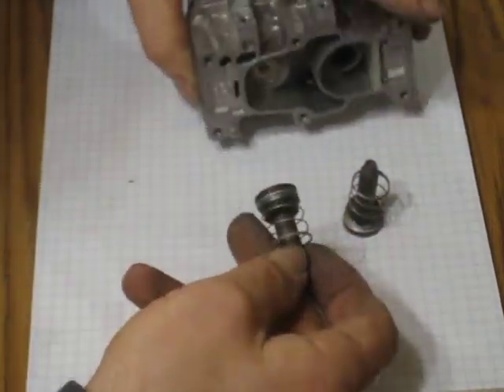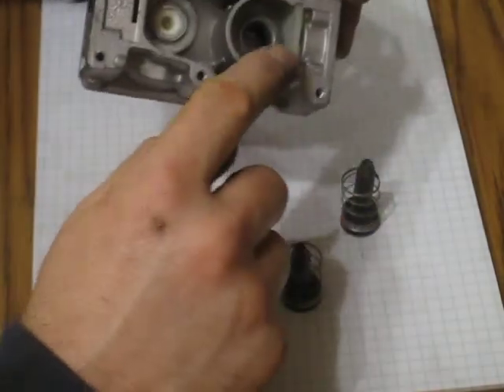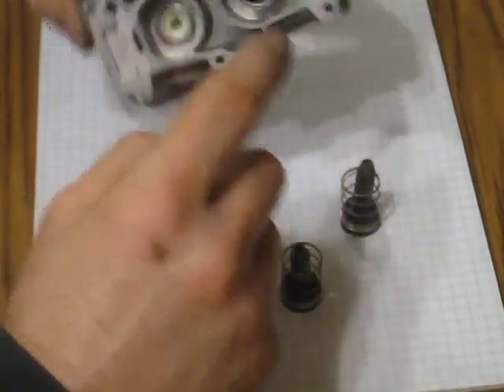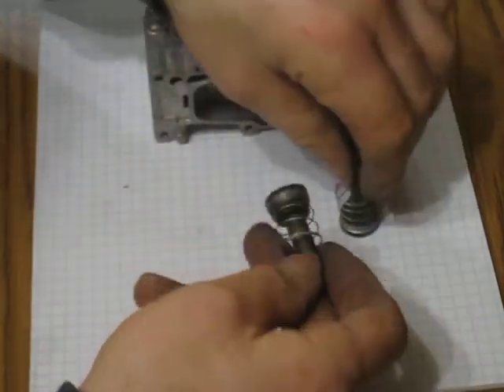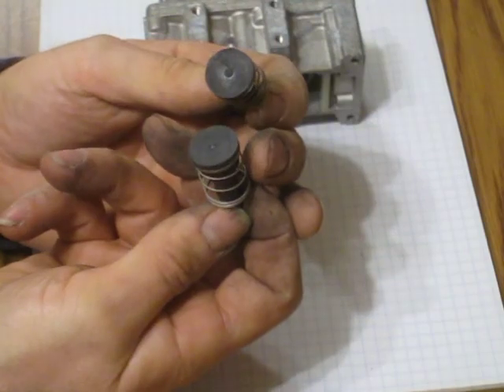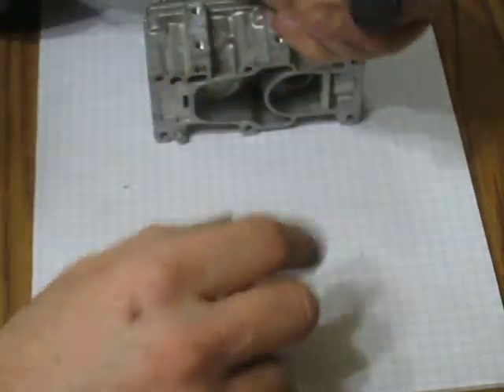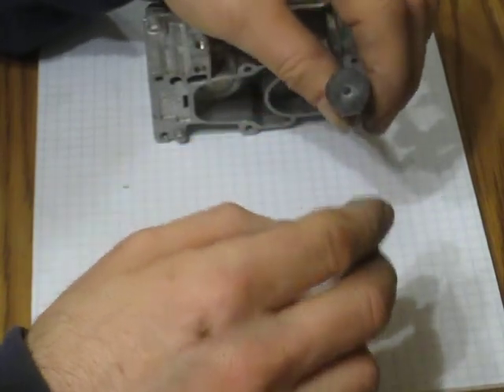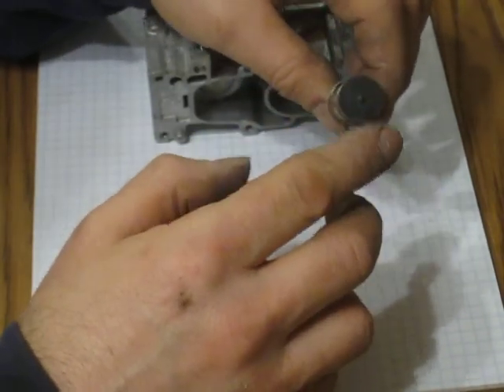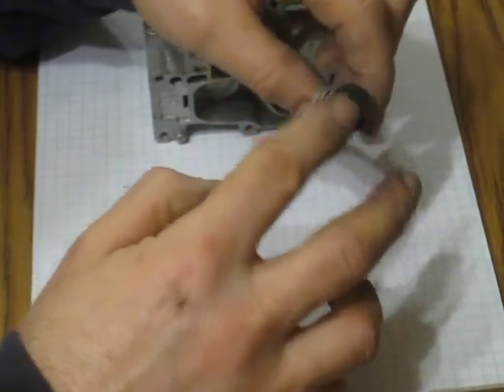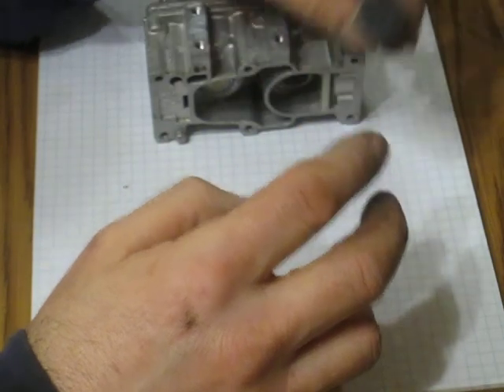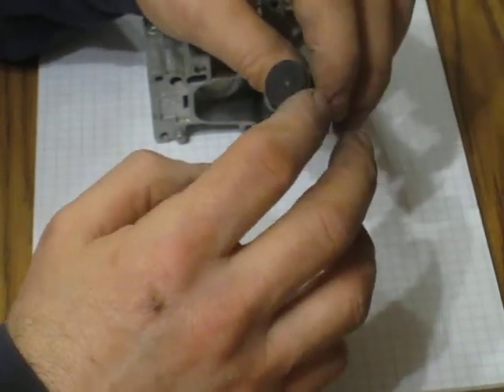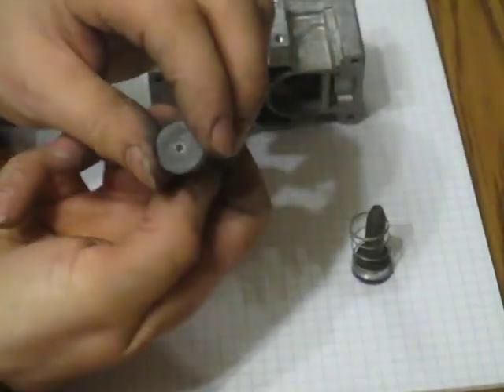In my case, this is what the inside looks like. You've got a little screen in here, so you can make sure that's clear. In my case, the faces of these two valves were slightly covered in some sort of corroded material. So I took some 600 grit sandpaper and sanded them in a circular pattern to remove all of the debris from both of them, so they're clean now.